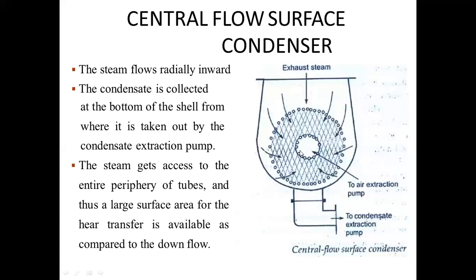Next one is central flow surface condenser. In case of central flow surface condenser, the steam flows radially inward. The condensate is collected at the bottom of the shell from where it is taken out by the condensate extraction pump. Here you can see there are a number of tubes in which water is circulating, and the exhaust steam which enters from the top or side moves radially inside, right?